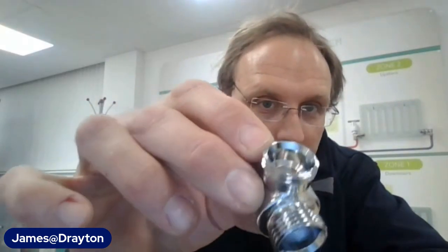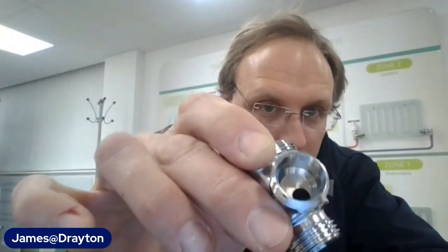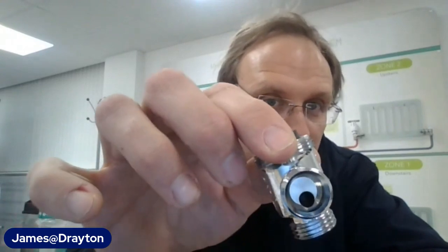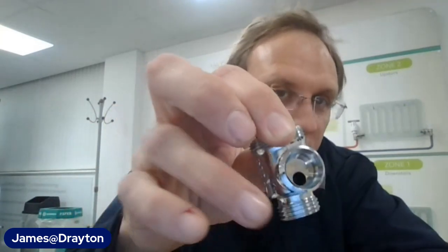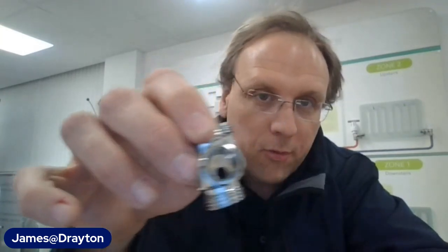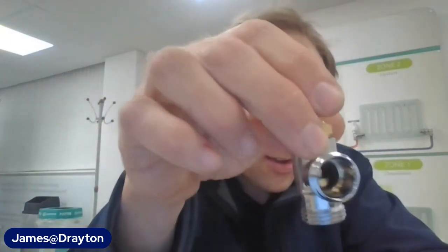So you've got really large ports either end. And you could quite easily use this lock shield with one of these, which is our EB body. But you can see that this EB body has much greater valve authority, even in the wide open position, just because there is more resistance to flow. There's more stuff in the way that prevents flow or restricts flow through the valve before you even start modifying your aperture.